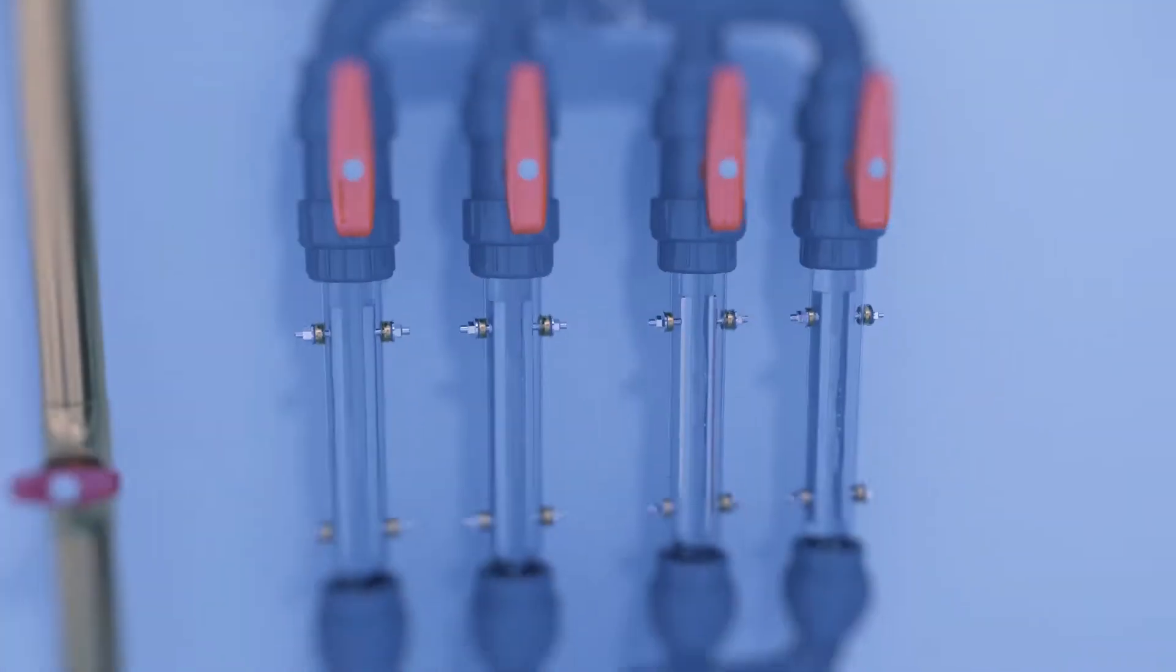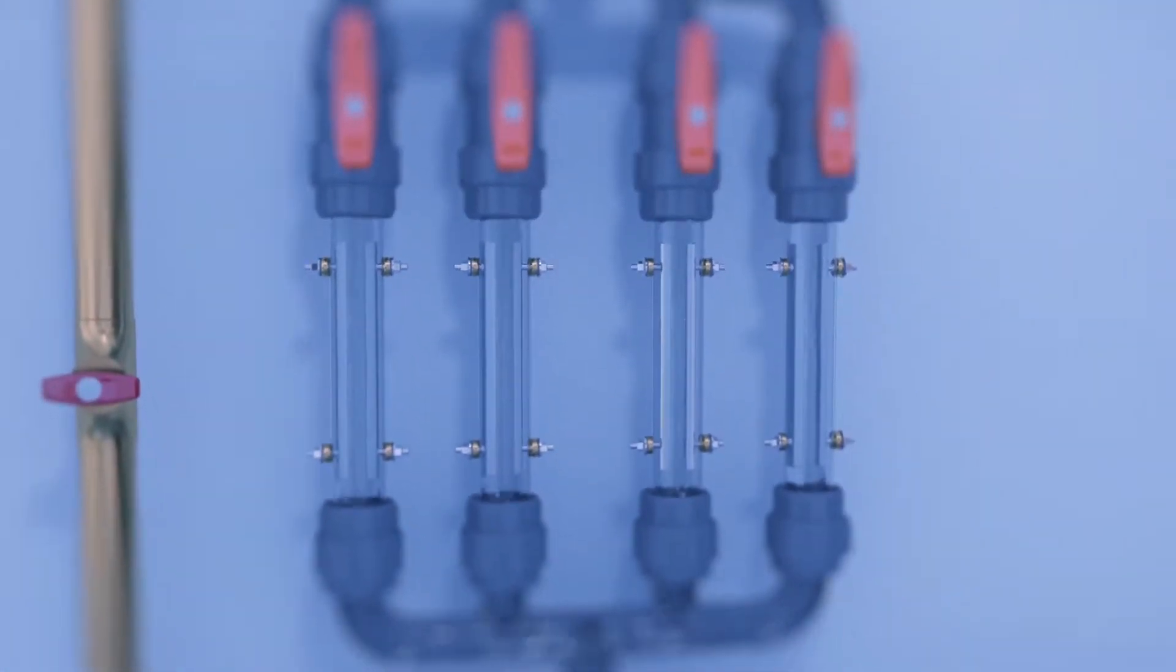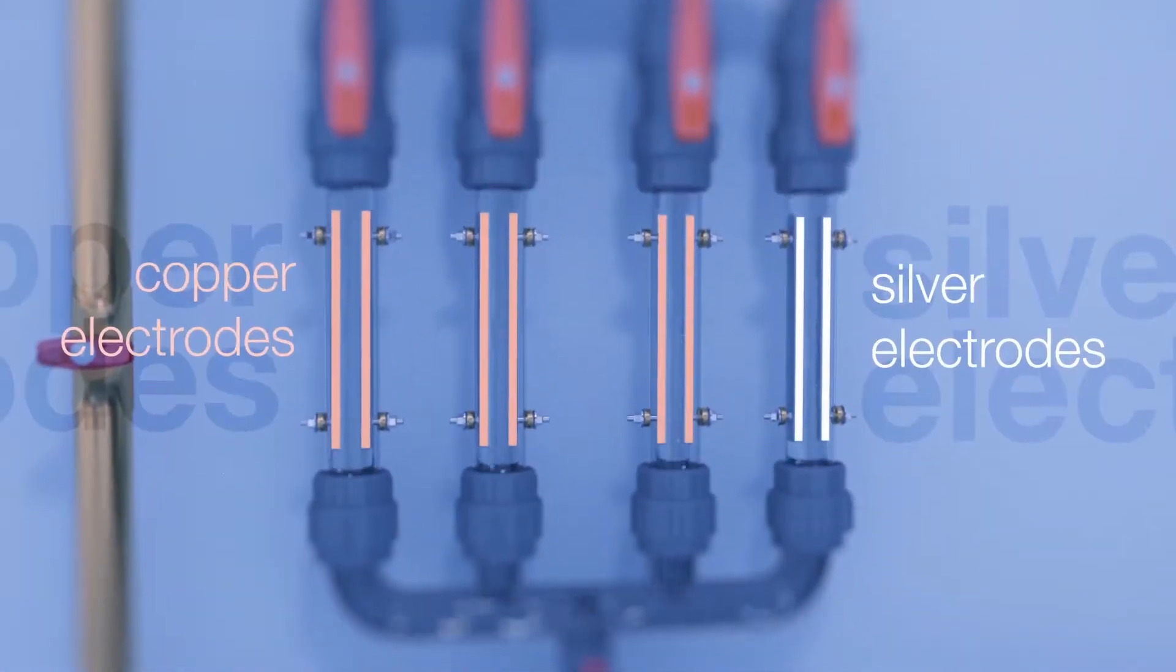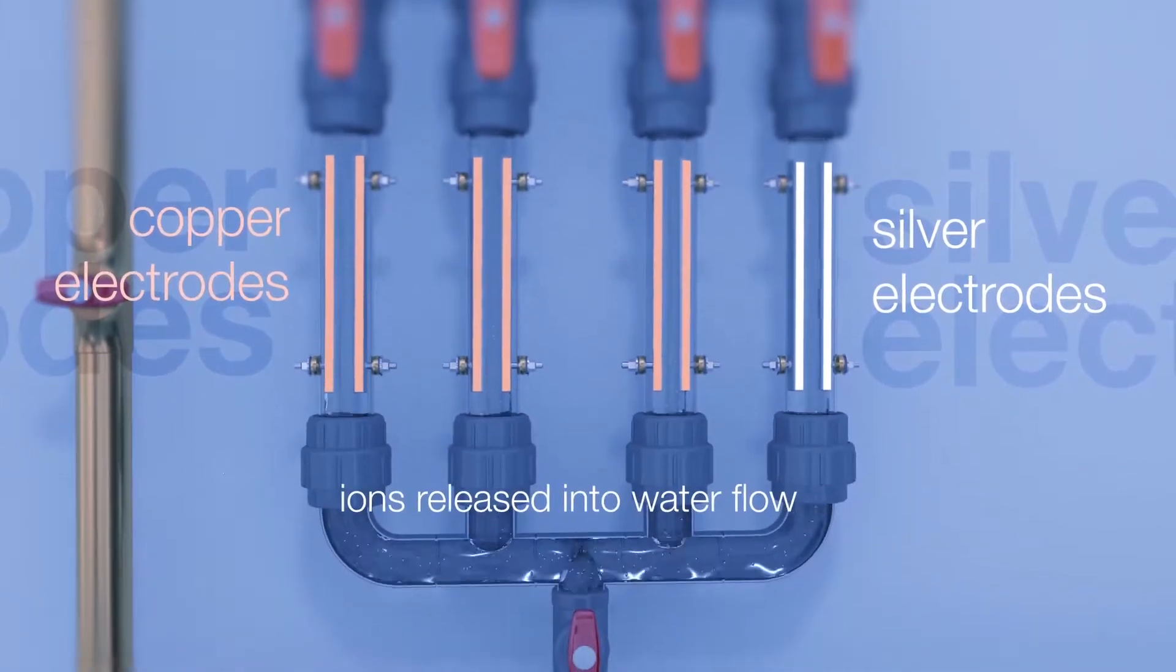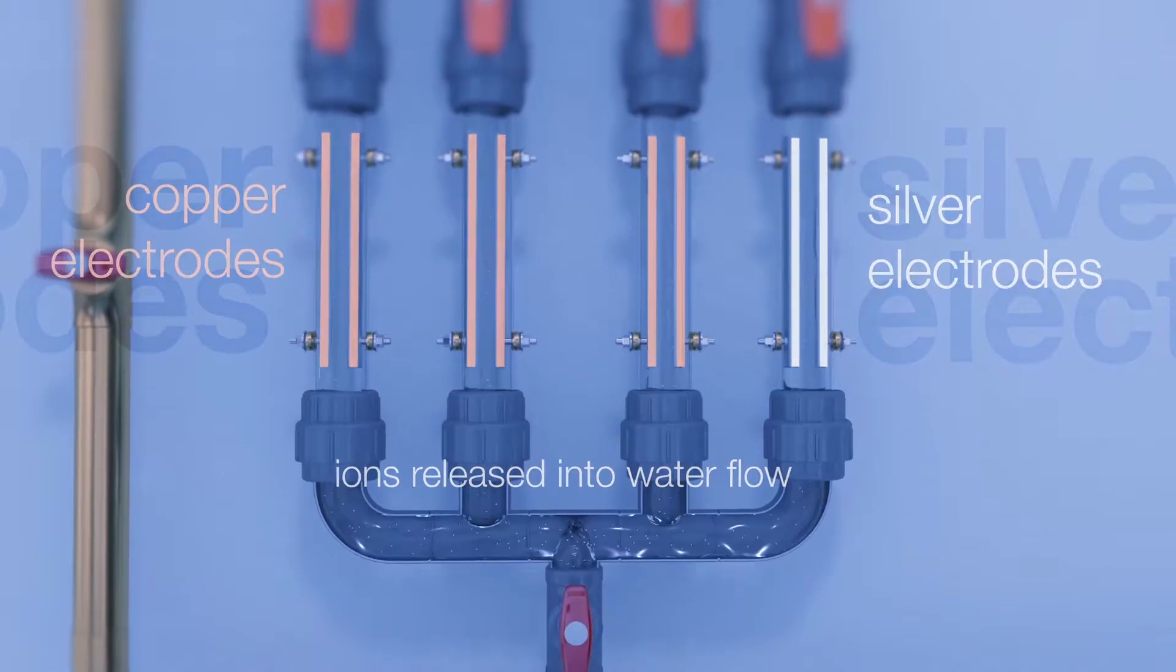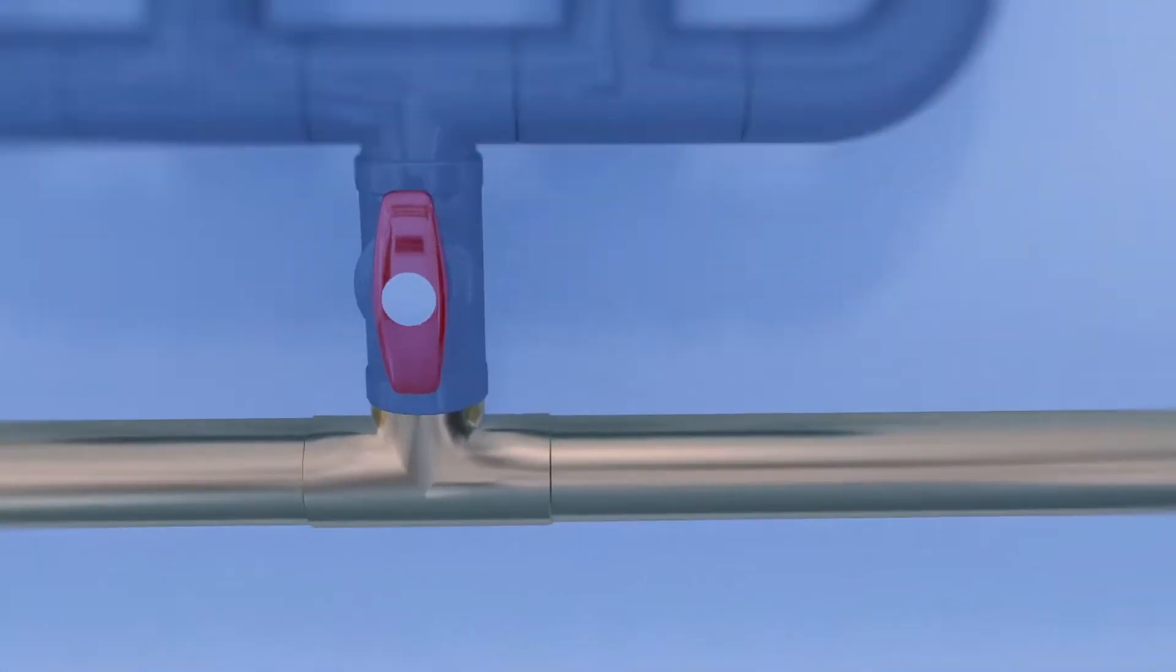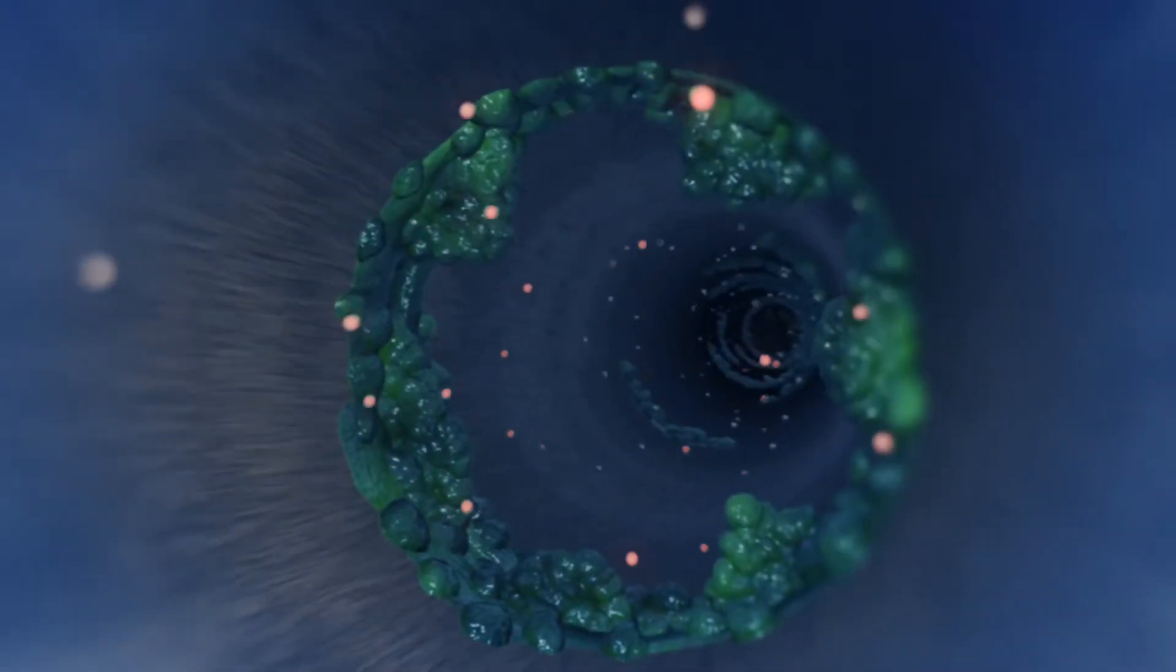The orca control unit then passes a low DC current between pairs of pure copper and pure silver electrodes. The current causes the release of electrically charged copper and silver ions, which are released proportionally depending upon differing flow rates.